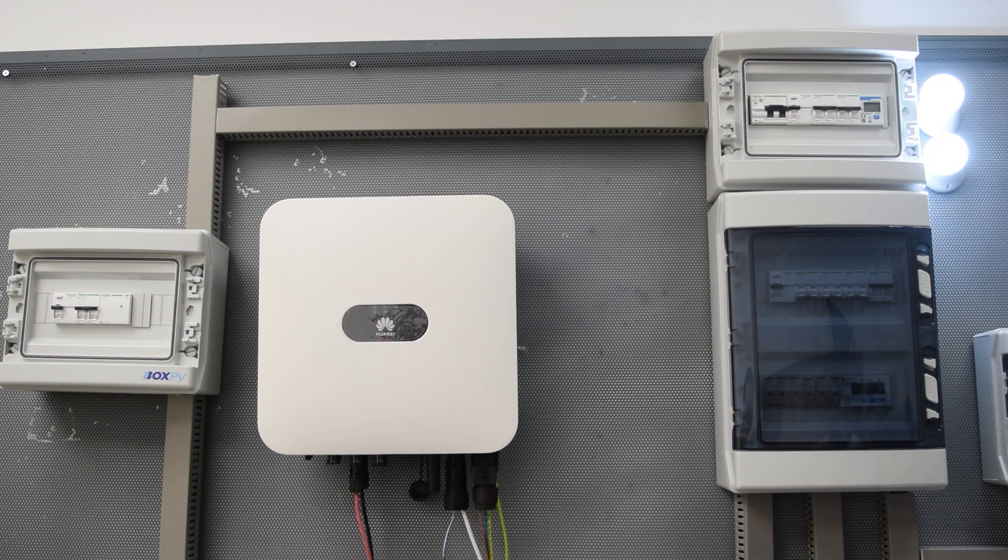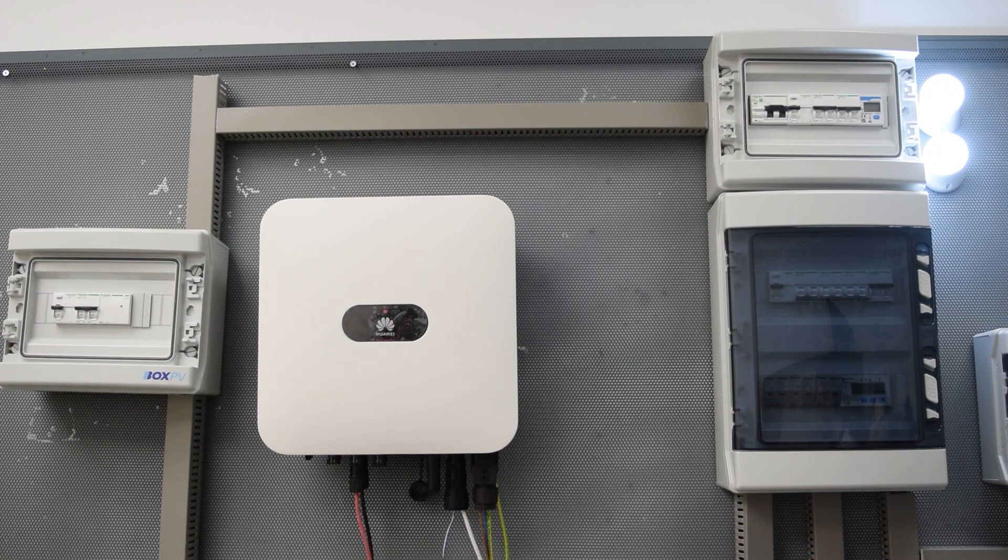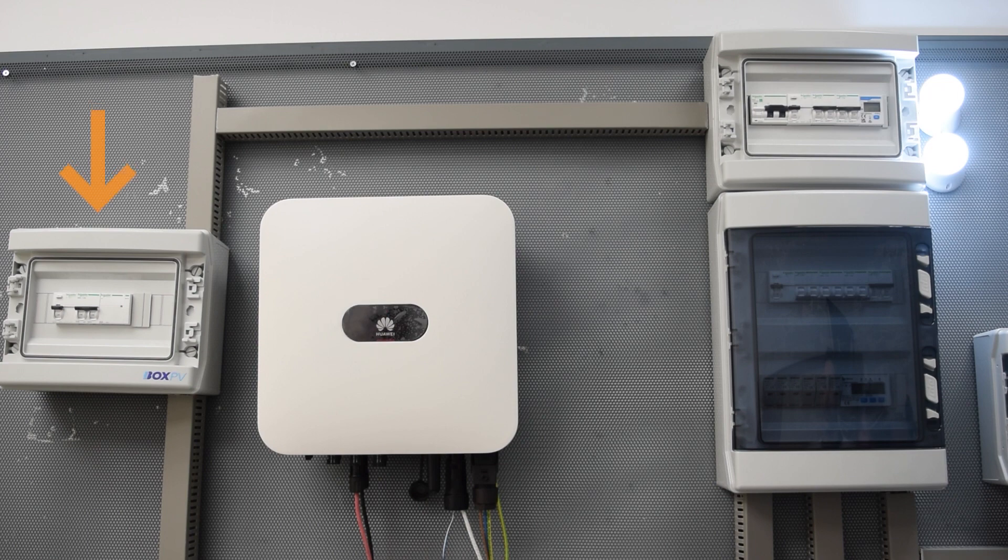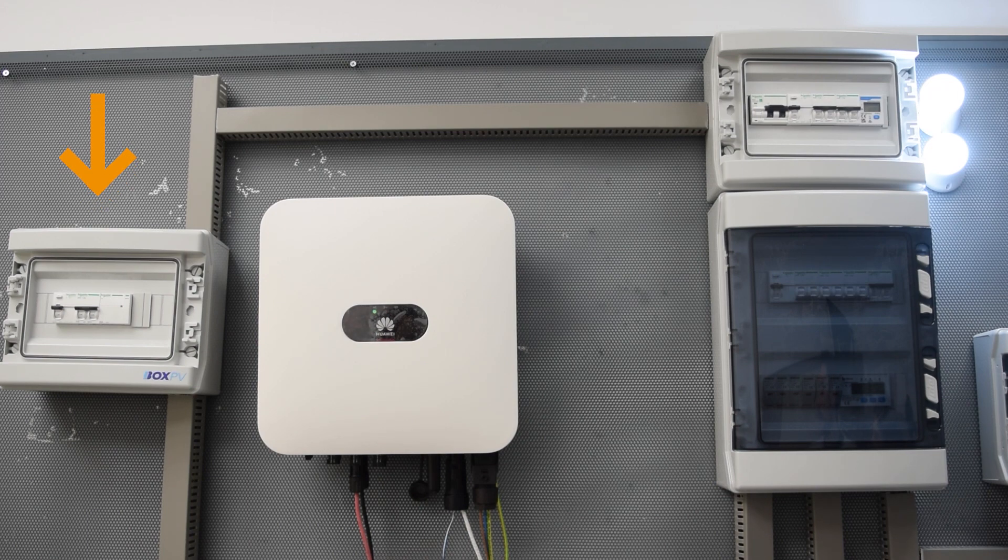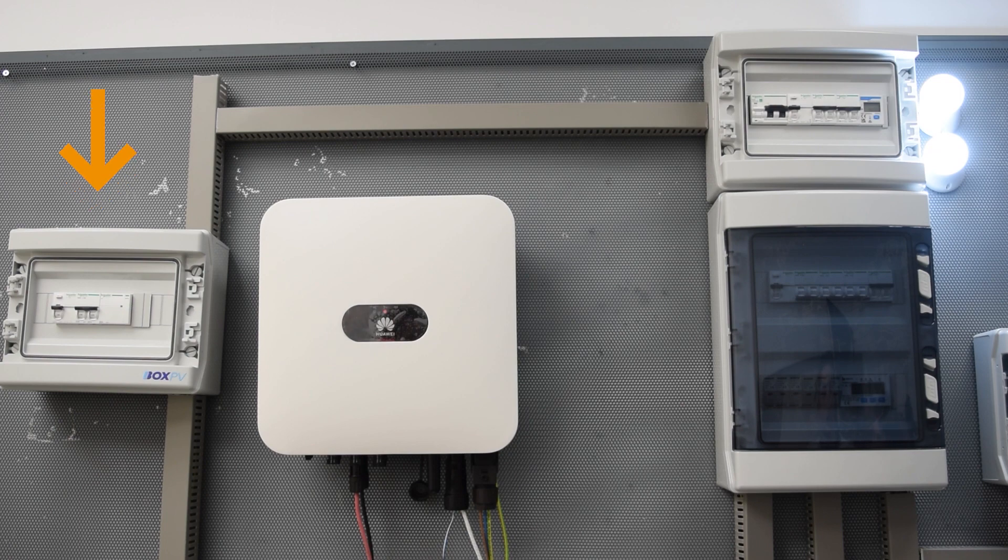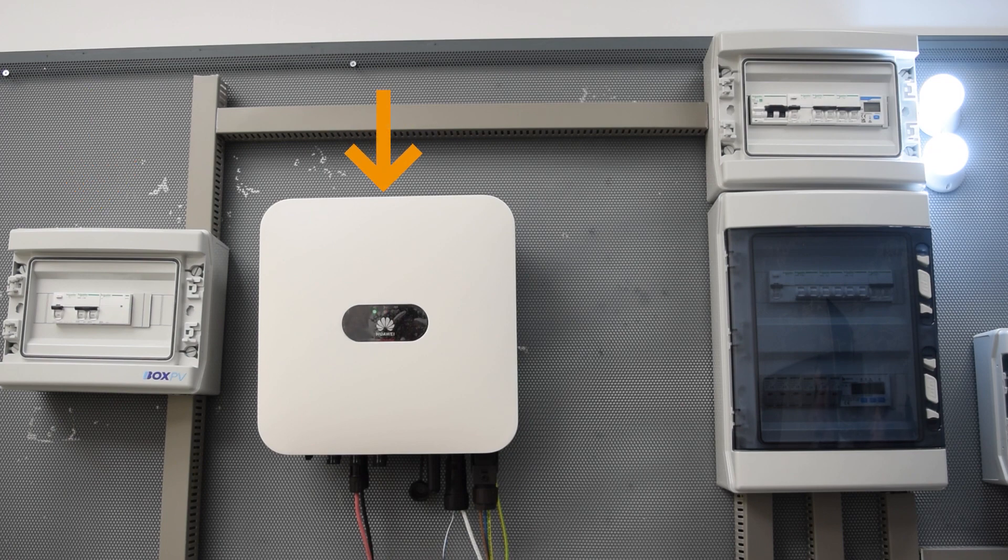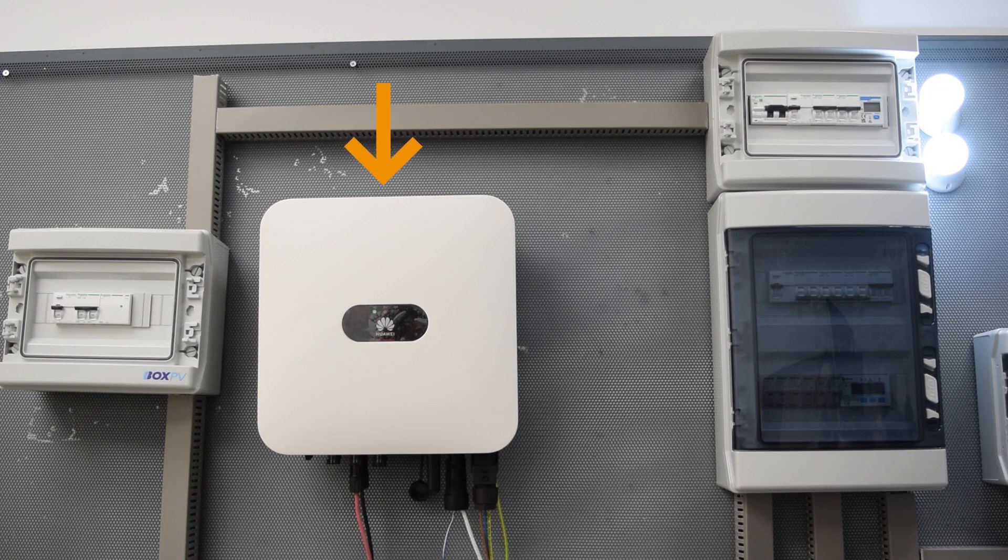This is because the backup box is responsible for isolating our system from the grid when we lose the connection to the grid, and for sending the corresponding signal to the inverter. This requirement is indispensable since it is strictly forbidden to give voltage to the grid when it fails or is cut off.